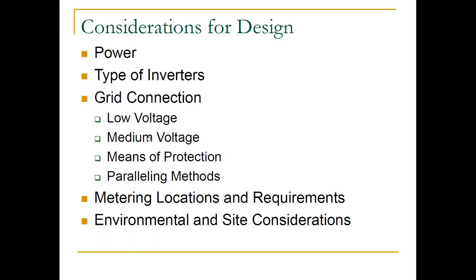So the considerations for the solar gardens that we're going to be focusing on here today is your power. How big of a garden are we talking? Is it going to be a 1 megawatt installation? Is it maybe a couple gardens tied together into a general area, or a little bit of a larger area of installation? Are we talking 5 megawatts? Are we up to utility scale installations where it's 100, 200, 300, 400 megawatt groups? Obviously, multiple groups of strings of inverters and switchboards and metering and transformers all tied together.